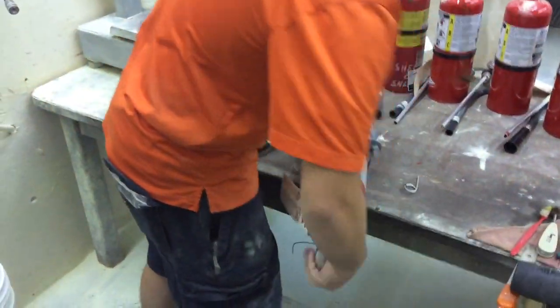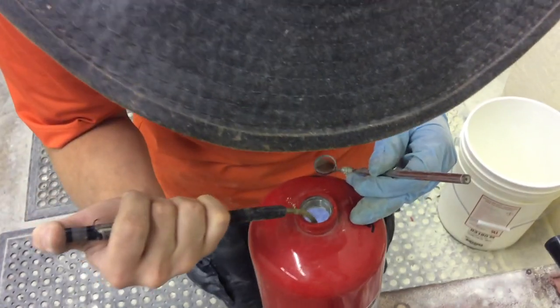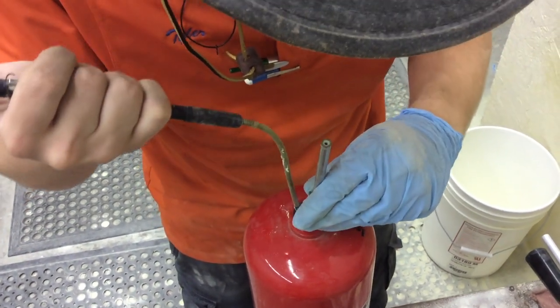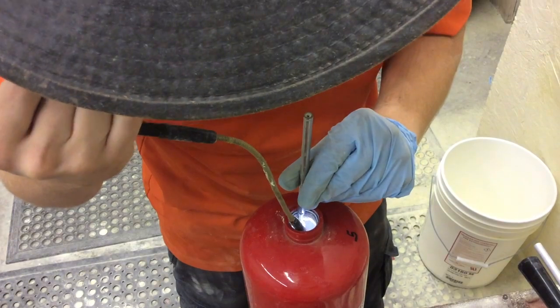Once the cylinder is emptied, it is devalved. The technician does a visual inspection of the inside of the cylinder with a flashlight and dental mirror to look for corrosion, cracks, or other deficiencies.